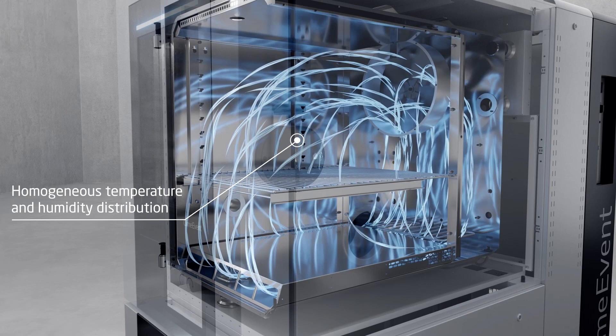The large axial fan draws the air from the test chamber. The air then flows over the enlarged water bath which ensures fast and precise humidification and dehumidification. Floor and ceiling baffles with additional perforations ensure homogeneous temperature and humidity distribution throughout the test chamber. With a new absolute humidity control, even higher control accuracy as well as improved transient behavior of the humidity is achieved, especially for alternating climate test runs and high dew points.